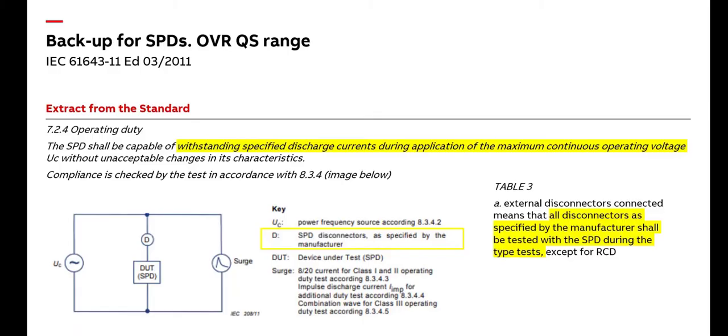Okay, so what does the SPD product standard exactly require from the backup of SPD? There are two main requirements. First one is the operation duty test. That means that during the normal operation of an SPD, the backup device does not intervene, allowing the SPD to do its work up to the maximum values of rated current, IMAX or IIMP, we declare for this product.